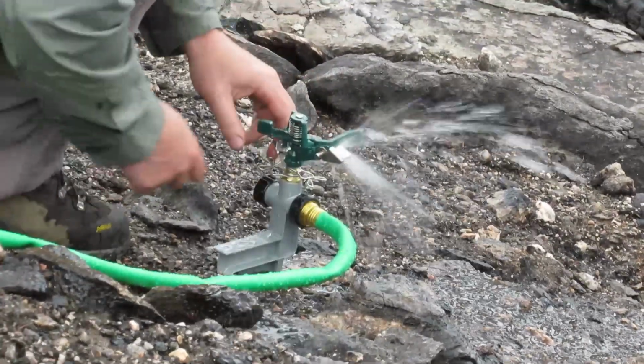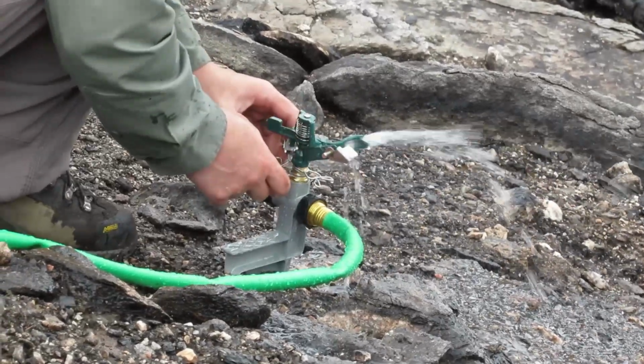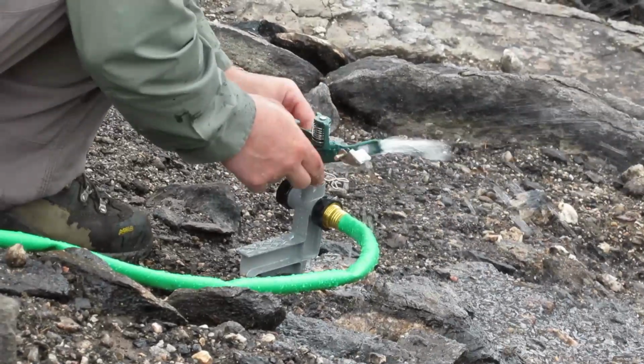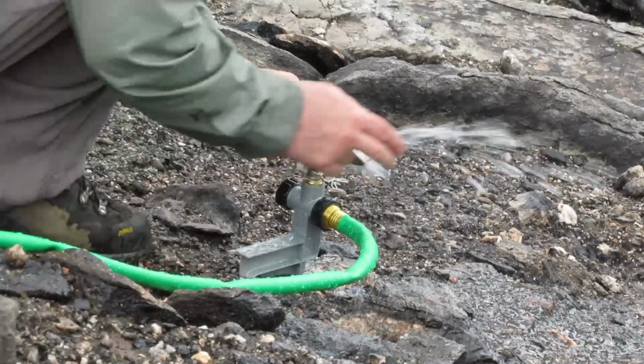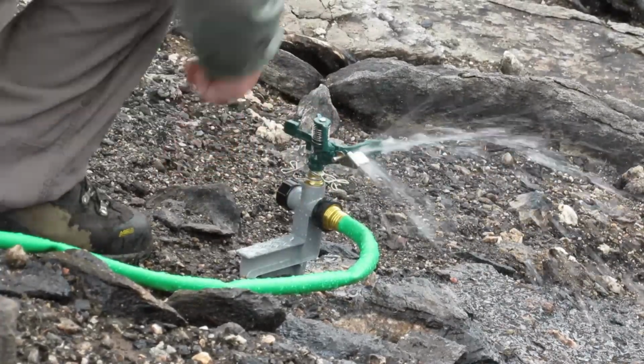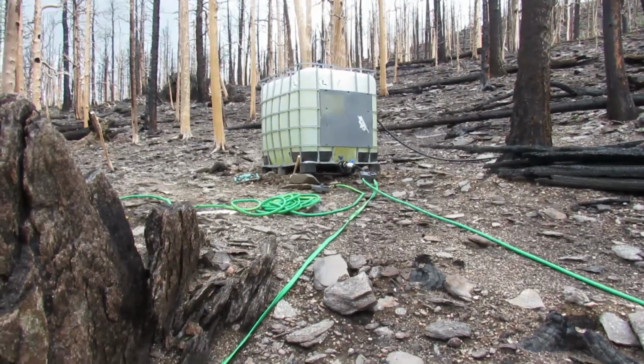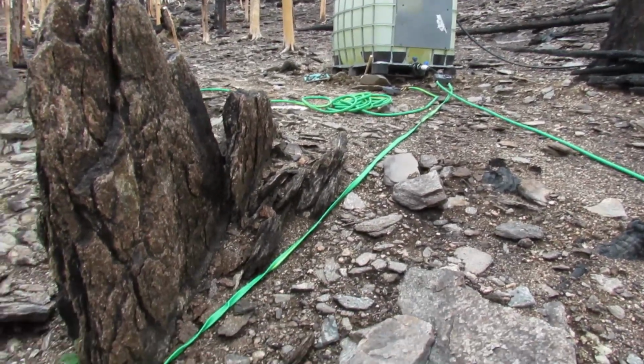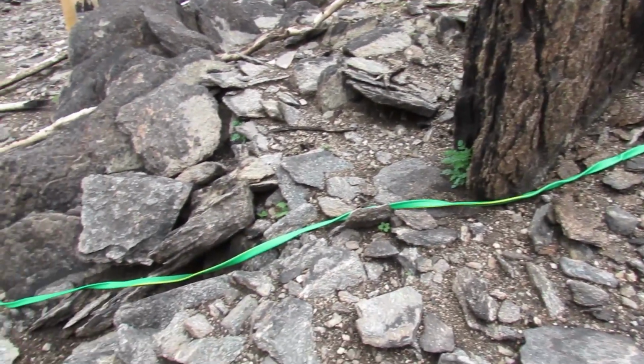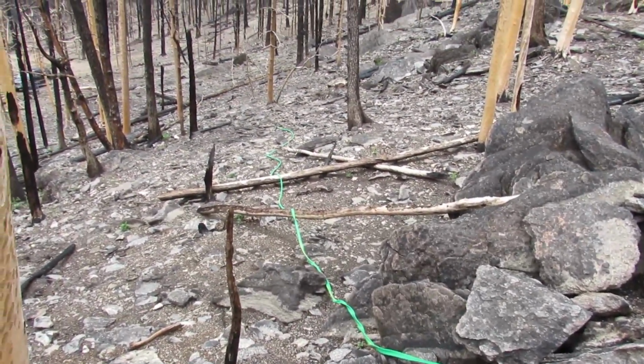We worked with the hoses for a while, but we still weren't getting enough pressure to the impact heads. Essentially, we had reduced the size of the pipe so much that the water volume was low enough that it wasn't getting enough volume and pressure down to the impact heads to have much effect. When we came back a little bit later, we even had the hoses collapse on us because it was trying to pull more water than could fit through the hoses. It looks like we have a little bit more work before we get this to function correctly.